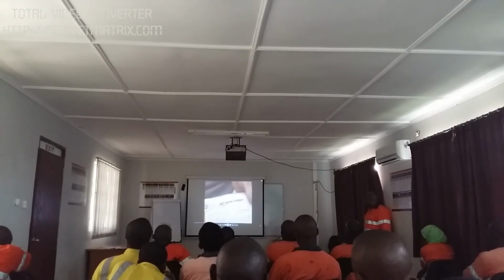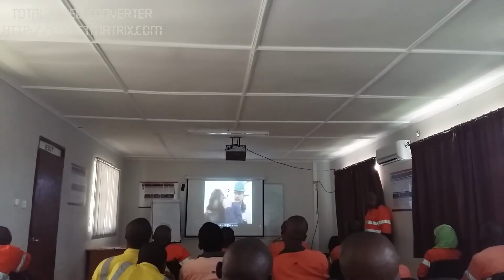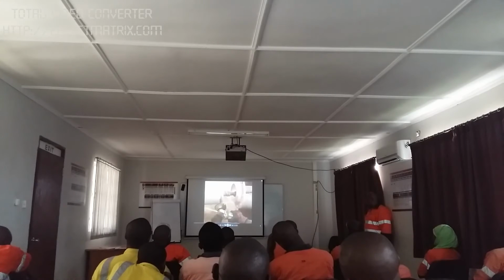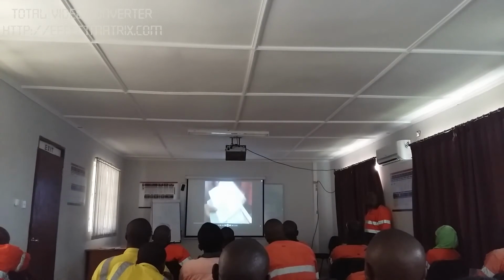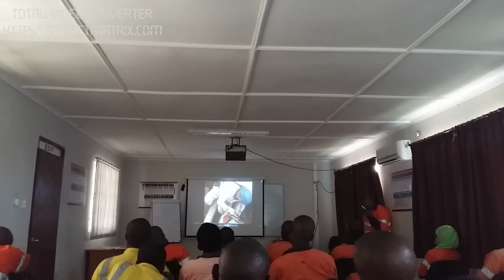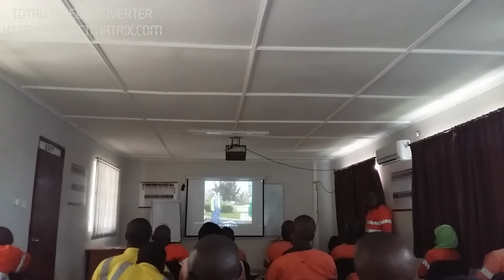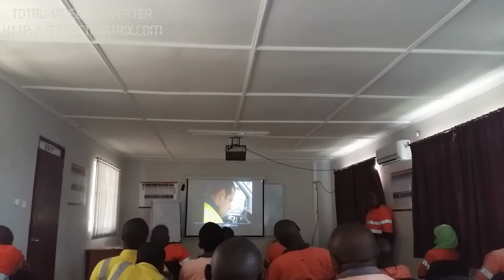The permit must define the scope of the work. It must identify hazards and assess risk. And it must establish control measures to eliminate or mitigate those hazards. The permit must link the work to other associated work permits or simultaneous operations. It must be authorized by the responsible person. And then everyone involved in the work must have the contents of the permit communicated to them. When the job is over, the permit must ensure adequate control over the return to normal operations. The permit provides written confirmation that a risk assessment of the specific conditions affecting the work has been carried out, and that appropriate control measures to protect personnel and equipment from each of the hazards have been provided.